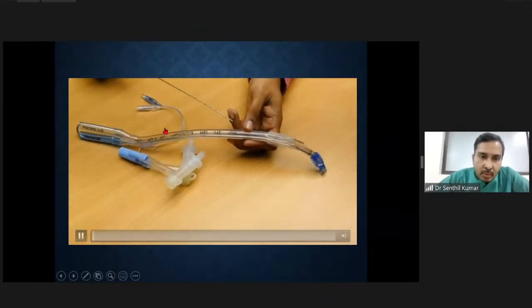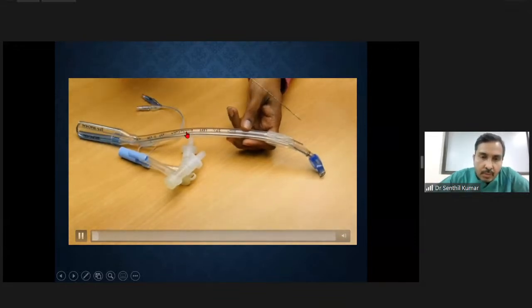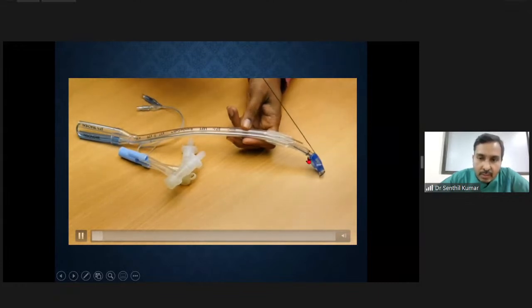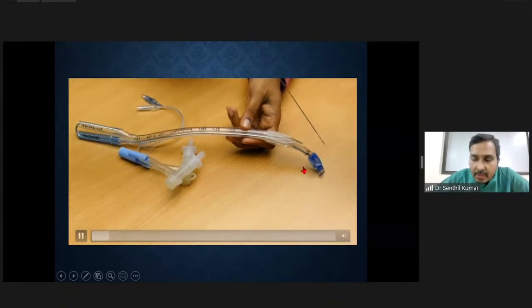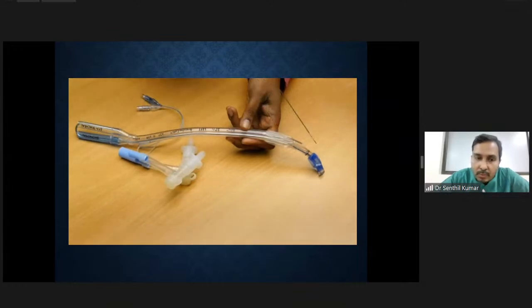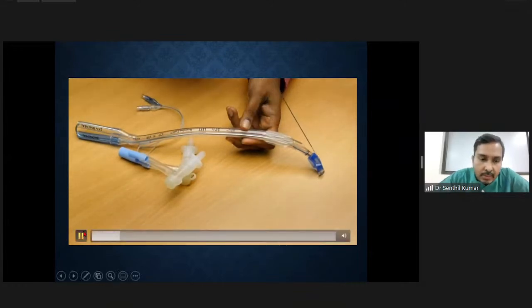See, this double lumen tube consists of two tubes sandwiched to form a single tube, and you have two channels. One is the tracheal channel, the second is the bronchial channel. Here you can see two cuffs in this tube. One is the blue colored bronchial cuff, which is a high pressure, low volume cuff. You are supposed to put 1.5 to 2 ml. When you inflate with more ml, it is going to produce damage. Bronchial rupture can occur.